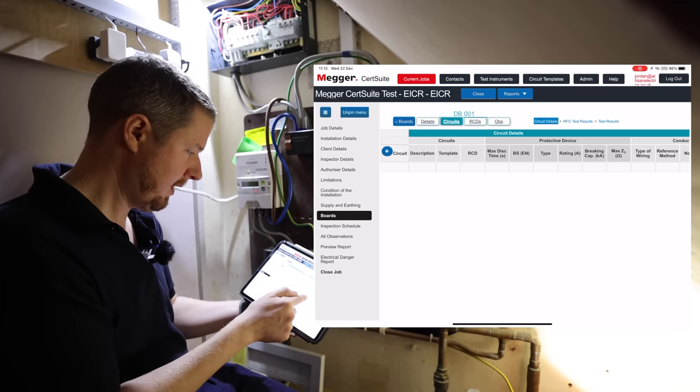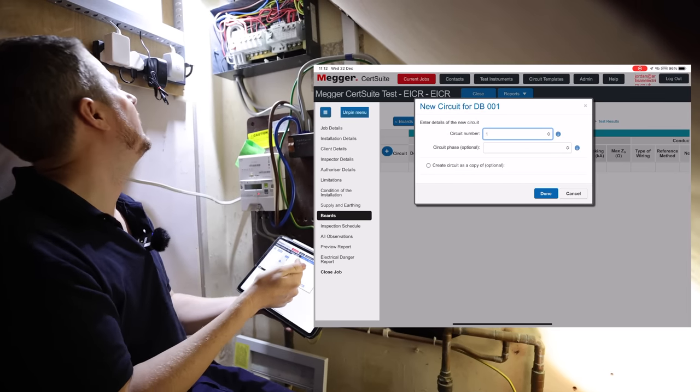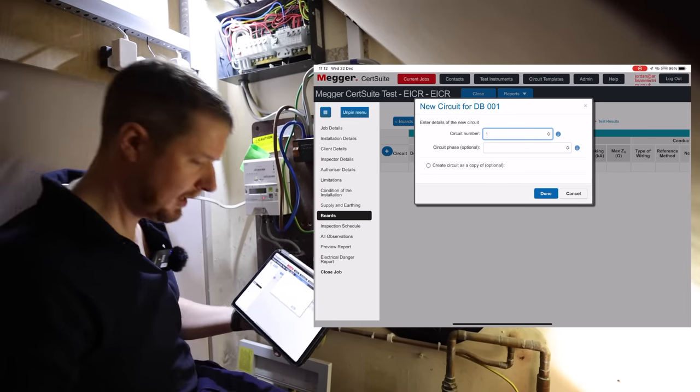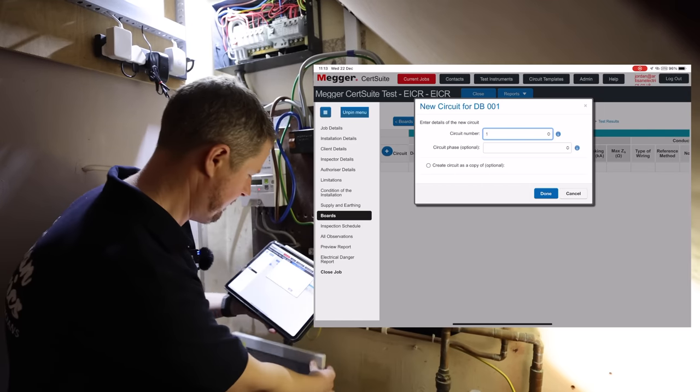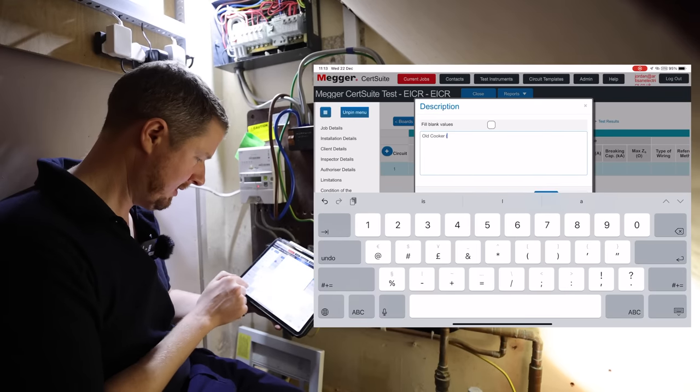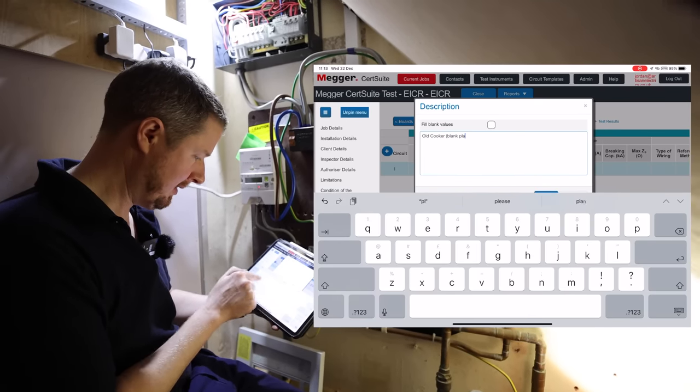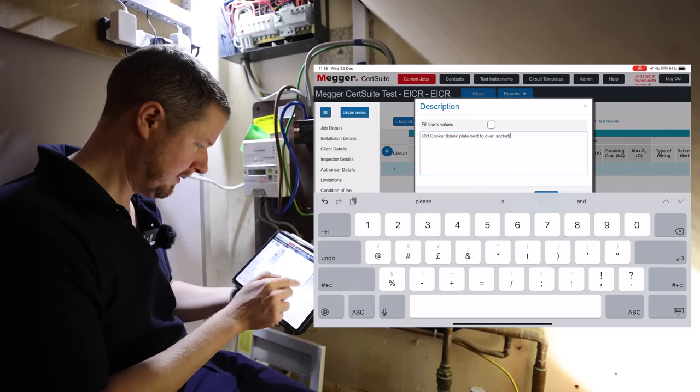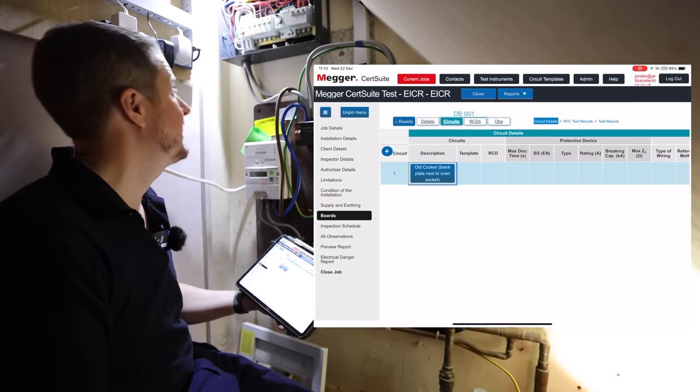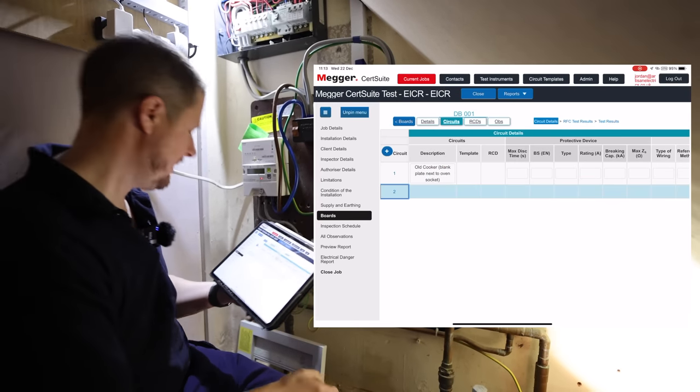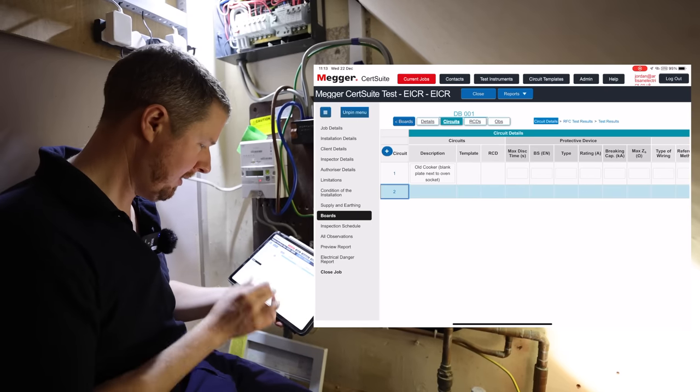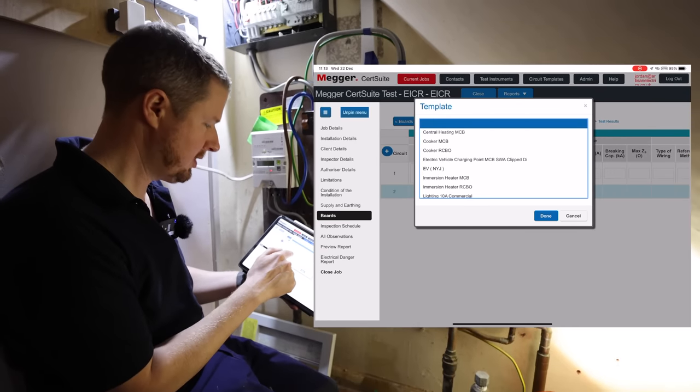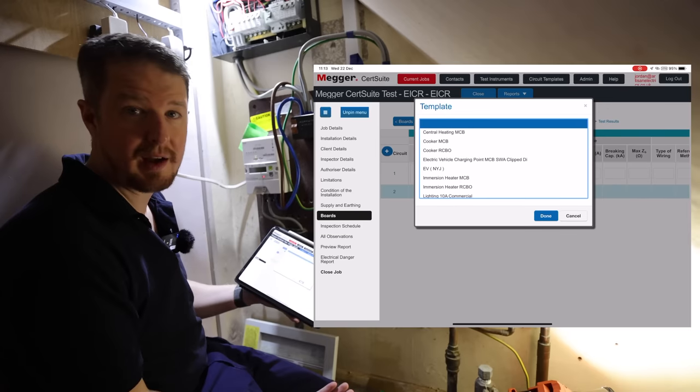Then what we're going to do is add our circuits individually, and we just start at the beginning and work our way through. So we will click add to create a new circuit. Circuit number one, 32 amp, and that is the, see what it's labeled as here, cooker. Now this is actually a redundant one, so we will just call it old cooker, and then I'll put brackets, blank plate next to oven socket. And we're not going to test that because it's not actually in use. We'll add a second circuit.